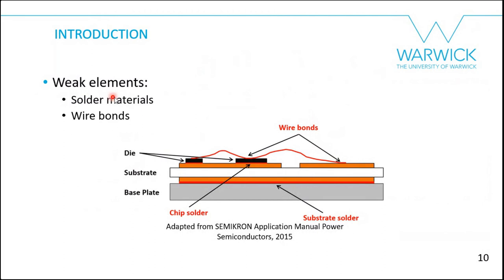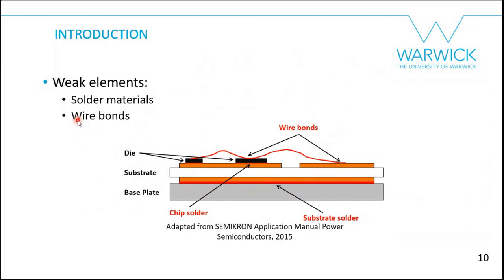Different studies have identified the weak elements of this packaging, which are mainly the solder materials and the wire bonds. Wire bonds interconnect chips and connect chips to copper areas on the substrate. Solder attaches the chips to the copper, and also attaches the DBC substrate to the base plate. These are the weak elements of the packaging system.